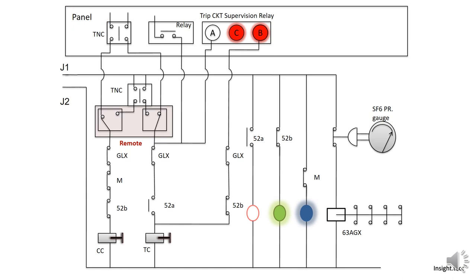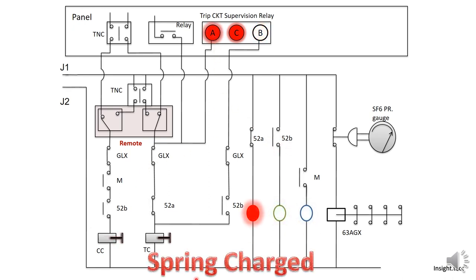Right now we have the breaker in the off mode with the local and remote switch on remote mode, so we are going to operate the circuit breaker from the control panel through the TNC switch. Once the TNC switch is operated, the closing coil is operated, due to which all the contacts will change and we have the post-close supervision indication. The spring is then once again charged and we get the spring charge indication back.